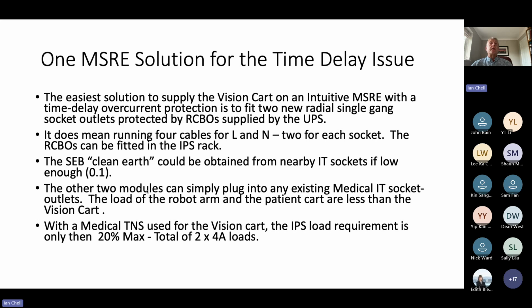So, going back to the medical surgical robot equipment, the easiest solution to supply the vision cart on the Intuitive medical surgical robot equipment, which I call the MSRE, was a time delay overcurrent protection device, is to fit two new radial single gang socket outlets protected by RCBOs supplied by the UPS. Okay, so if it's a retrofit, this means fitting 4 cables, two for live, two for neutral, and the RCBOs. The two new RCBOs can be fitted in the IPS rack.